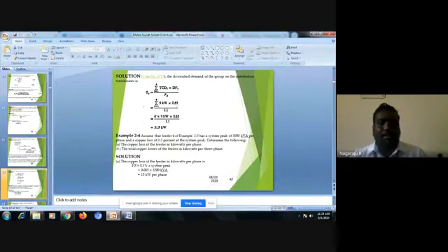Common demand, one or two times it is repeated. Diversified demand is equal to total connected load. Each load is connected to the 9 kilowatts he gave. So 6 into 9, divided by demand factor. Demand factor is 0.65 he gave. Divided by diversified factor. Diversified factor is equal to 1.1. This answer is 31.9 kilowatts.